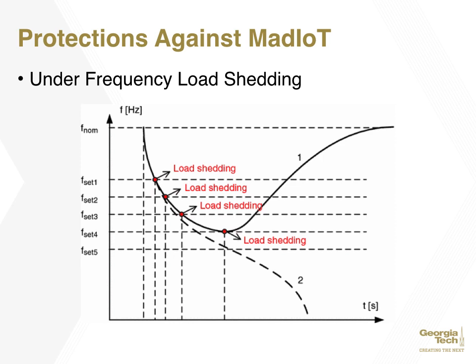The next was mentioned in a previous slide, comparing past research to the current research done in this paper, and that is under-frequency load shedding. It is a countermeasure applied by bulk power system operators to reduce the incidence of generator under-frequency tripping, which is a great danger to the reliable operation of the power systems. UFLS for short is a coordinated disconnection of small and non-critical components to prevent a large blackout, but also accounts for some components which should be disconnected absolute last if at all, such as hospitals, police stations, and other critical services.